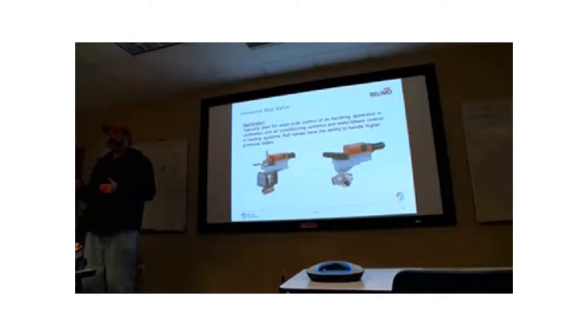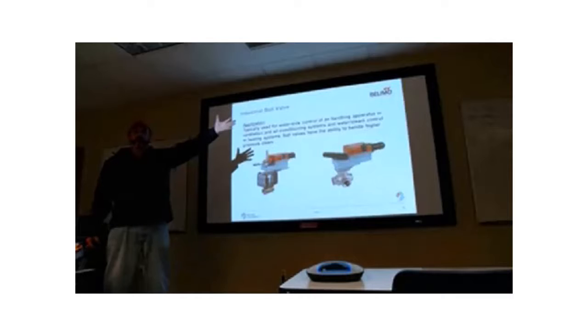If you guys are ever involved in replacing valves on what we call atmospheric systems. What I mean by that is, say you've got a makeup water tank. You know what I mean by a makeup water tank, right? It's makeup for the chiller or the boiler. So you might be dumping water into that tank. Maybe you've got a 50 PSI supply, and you're opening up that valve. It's just dumping water into an open tank. Well, that valve that opens and shuts has 50 PSI on the upstream side, and what does it have on the downstream side? 0 gauge, right? You've got 50 PSI gauge, and you've got 0 gauge.